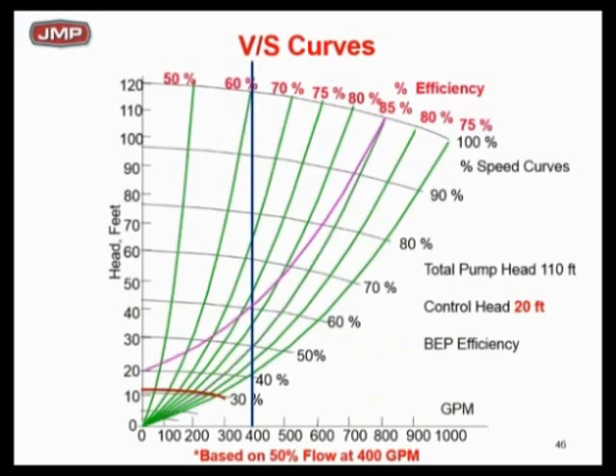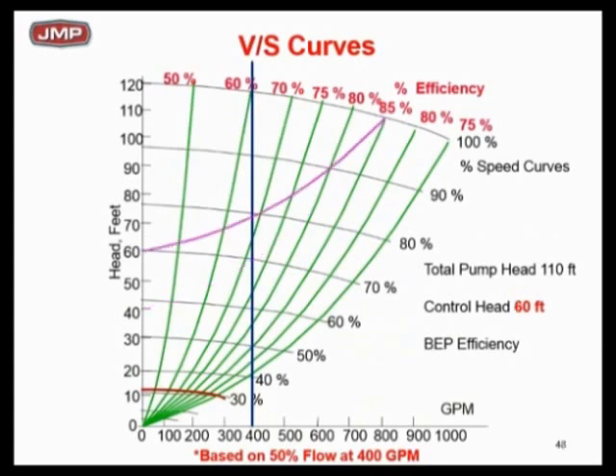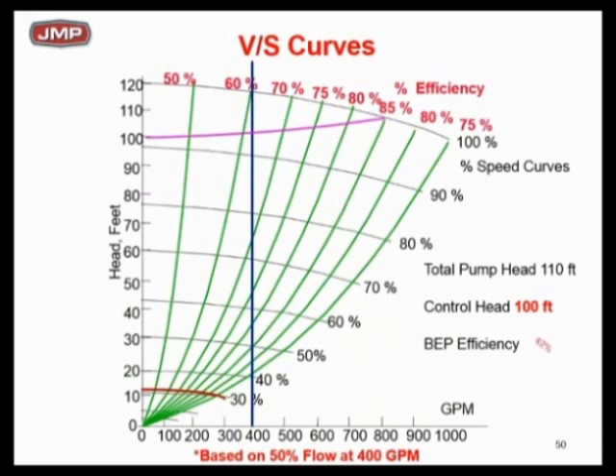Continuing to increase constant head: at 40 feet constant, BEP efficiency at half flow drops to about 72%. At 60 feet constant — 50 feet variable — best efficiency is now 67%, and at zero flow I need about 70% speed. At 80 feet constant, efficiency is about 65%; at 100 feet constant, about 62%. You can see the message: constant head will not change your speed, and BEP efficiency goes down as you increase the constant head. The only thing that changes speed and preserves efficiency is variable head.